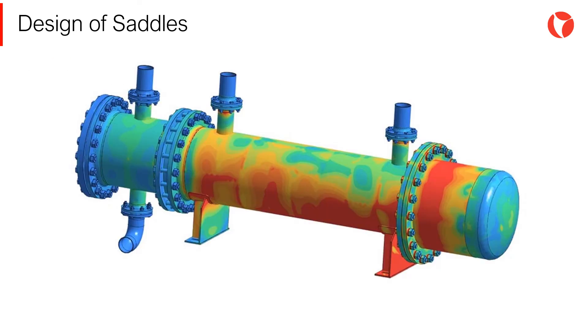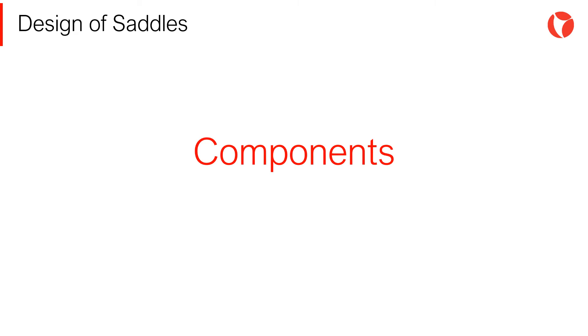After locating the saddles, the shell should be verified against overstresses. This can be verified as per the Zick method, or by means of finite element analysis. Depending on the type of exchanger and project requirements, there are different configurations and designs of saddles to support this type of equipment. Next, the most commonly used configurations will be shown.